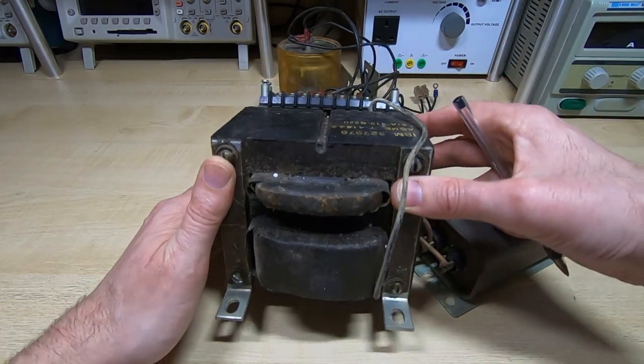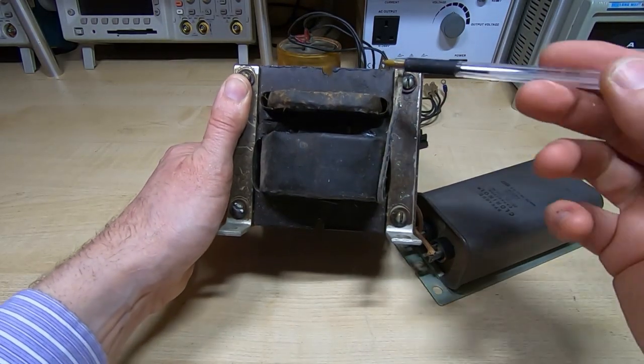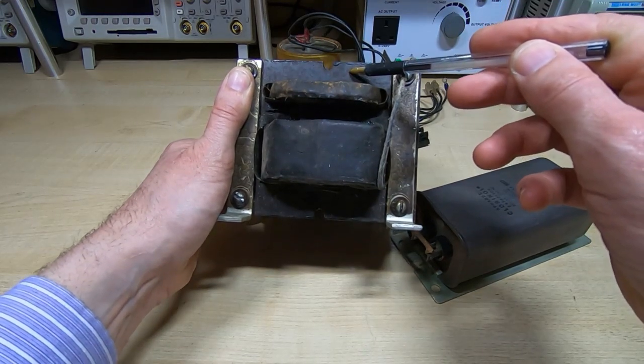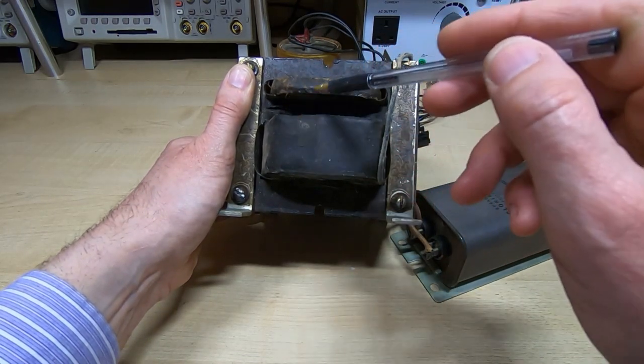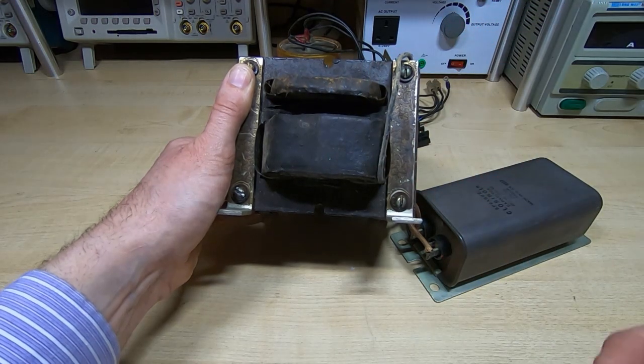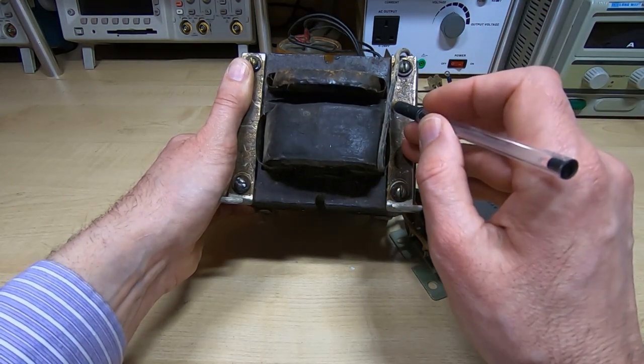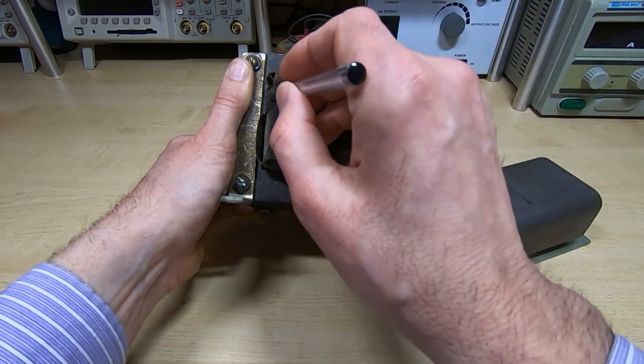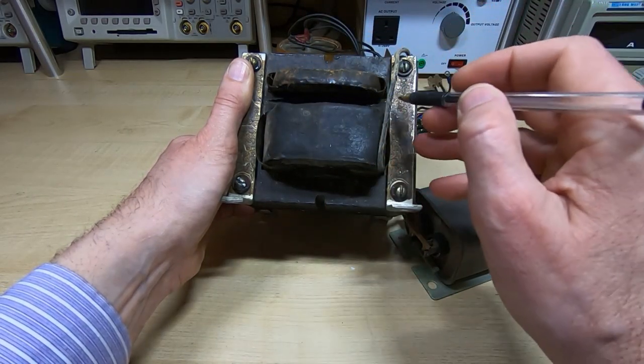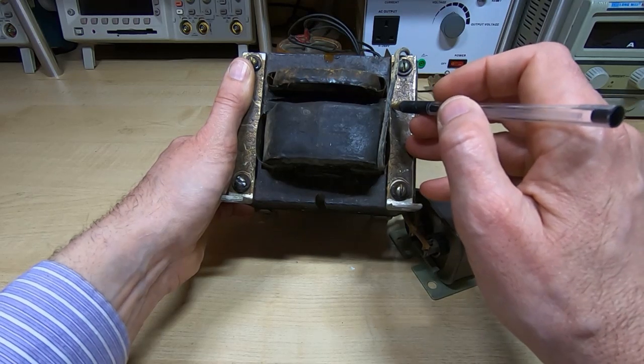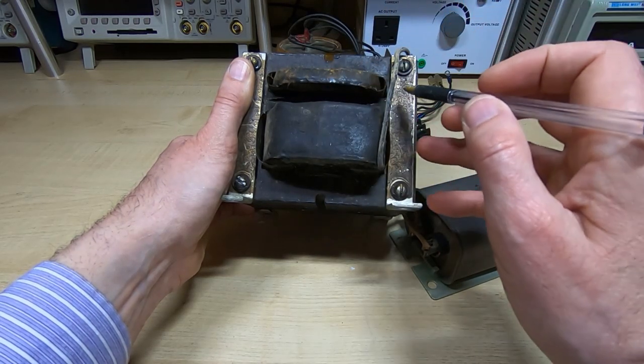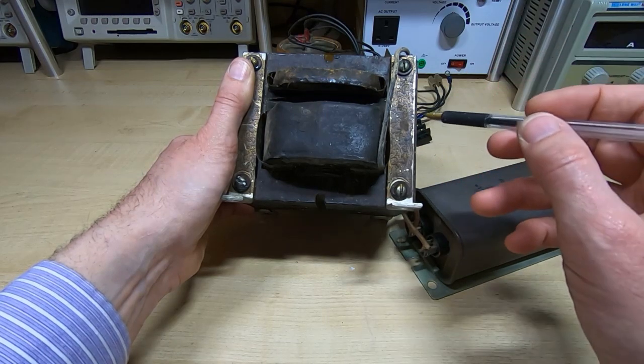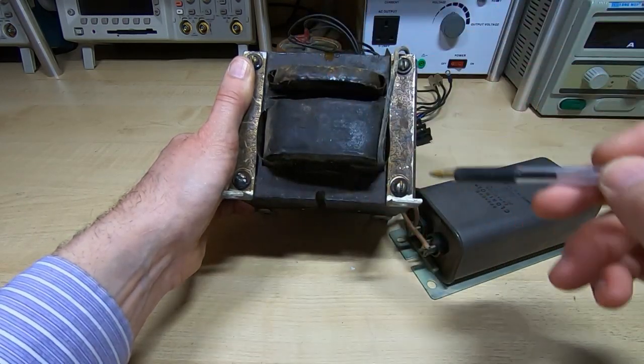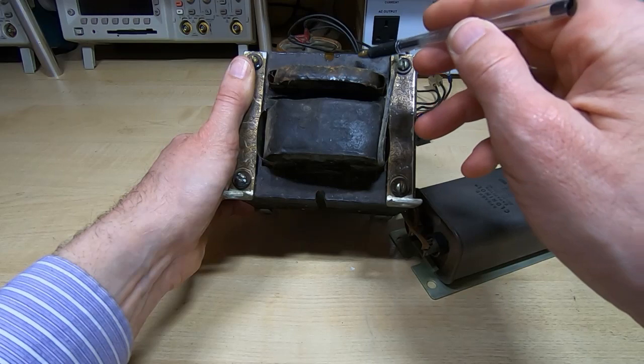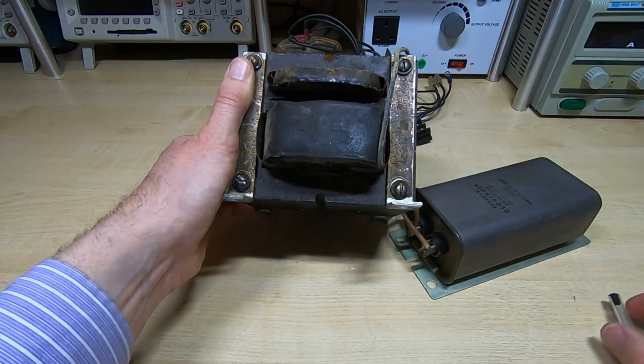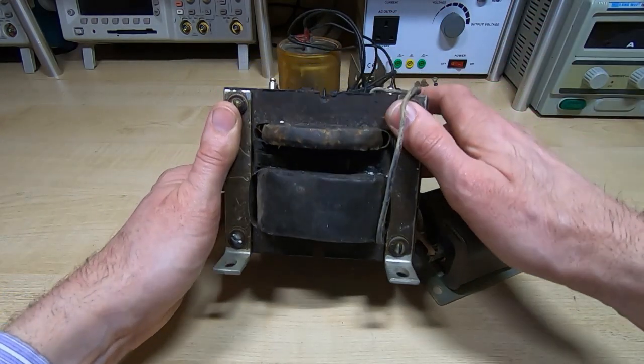Okay, so that's the way it's structured. There's nothing else in here. It is just laminations making a standard core, a couple of windings and the magnetic shunt. One thing you can't see is there is air gaps down between each side of the magnetic shunt, and they're quite important to the operation in terms of setting its performance and operating point. And again, I'll come back to that later on, but just bear in mind that the general structure is laminations, shunt and the windings themselves. So I'll just get this out of the way.